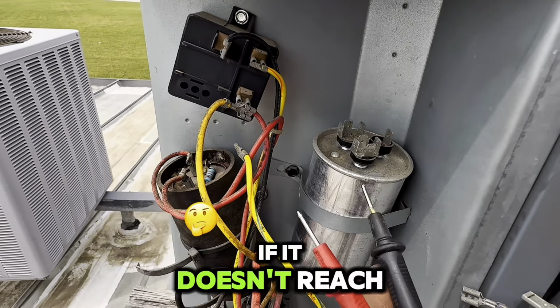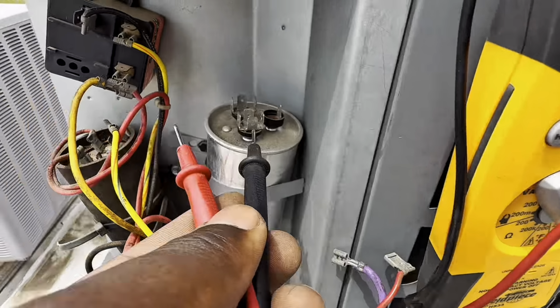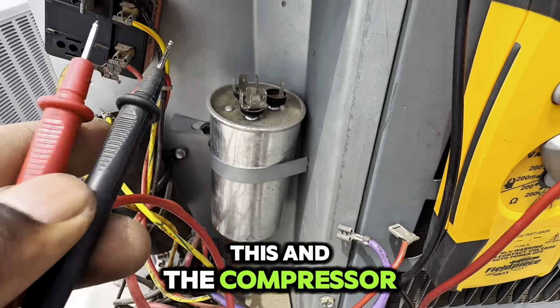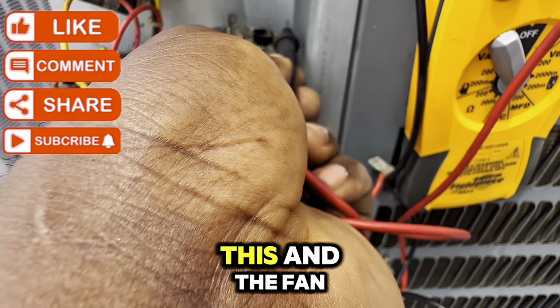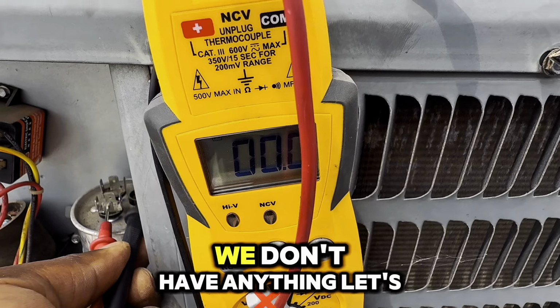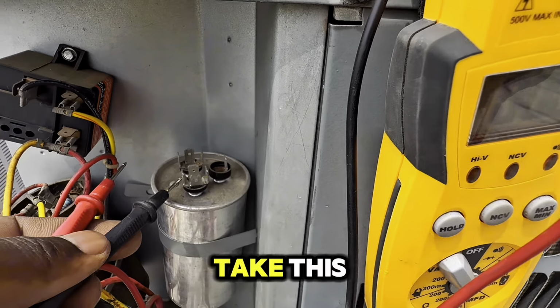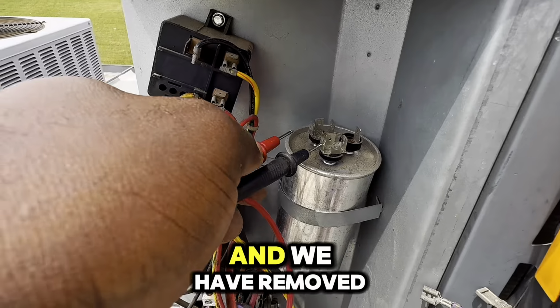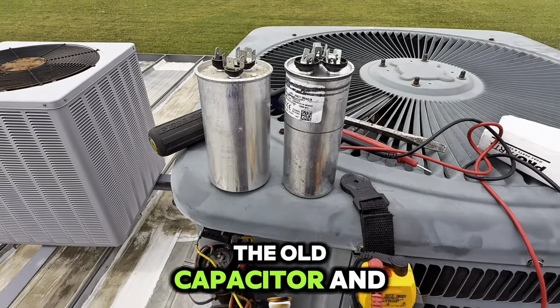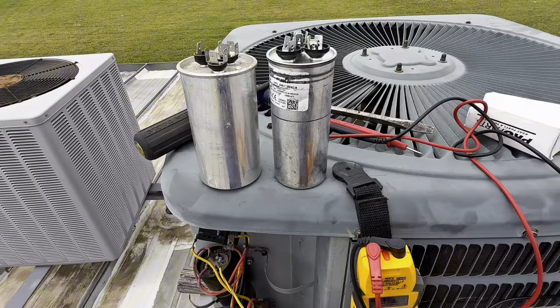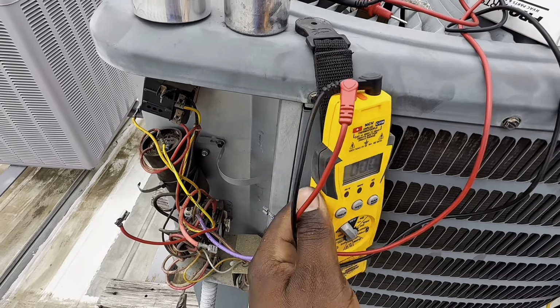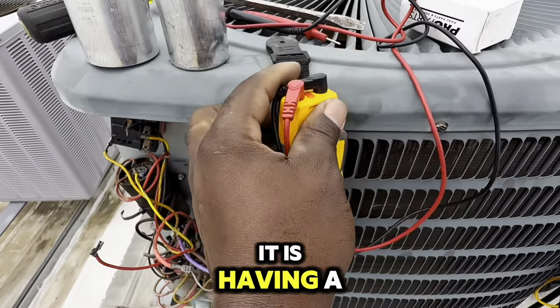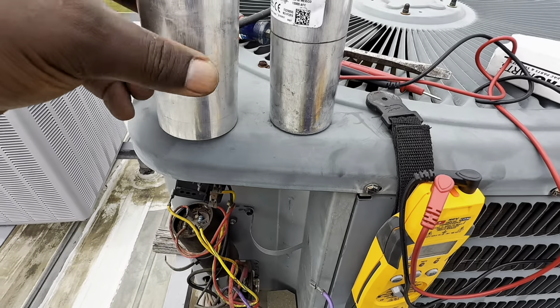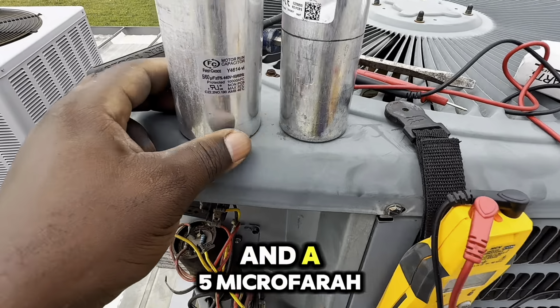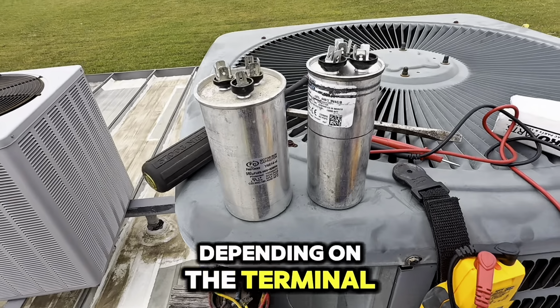Okay, if it doesn't reach 5 microfarad, that means it's not working. With the common and this and the compressor, we should reach 60. I think this is 60. So let's start with this and the fan that is not working. We don't have anything. Let's take this, and we have removed the old capacitor, and we're gonna see if actually it is having the 60 microfarad and the 5 microfarad, depending on the terminal, right?